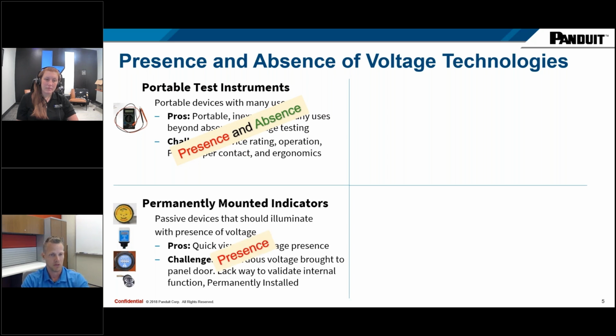They are typically used for presence of voltage, mainly because you can't validate that they are functioning properly. If a solder point came loose or blew a fuse or some sort of electrical component in the PCBAs that are inside of these devices, you can't verify that they're working properly. So that's why you can't use them for just absence of voltage testing, just because the lights go off.